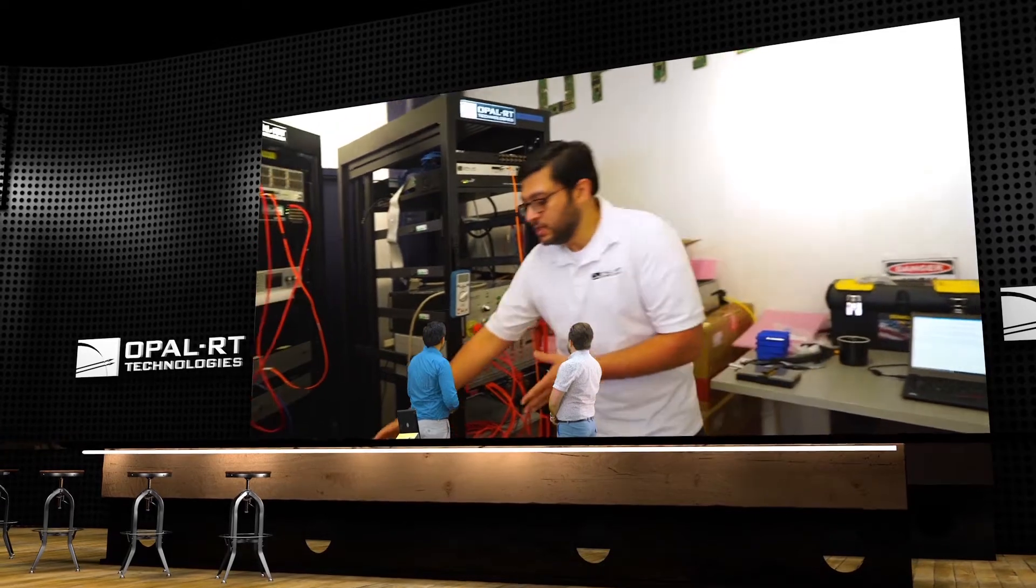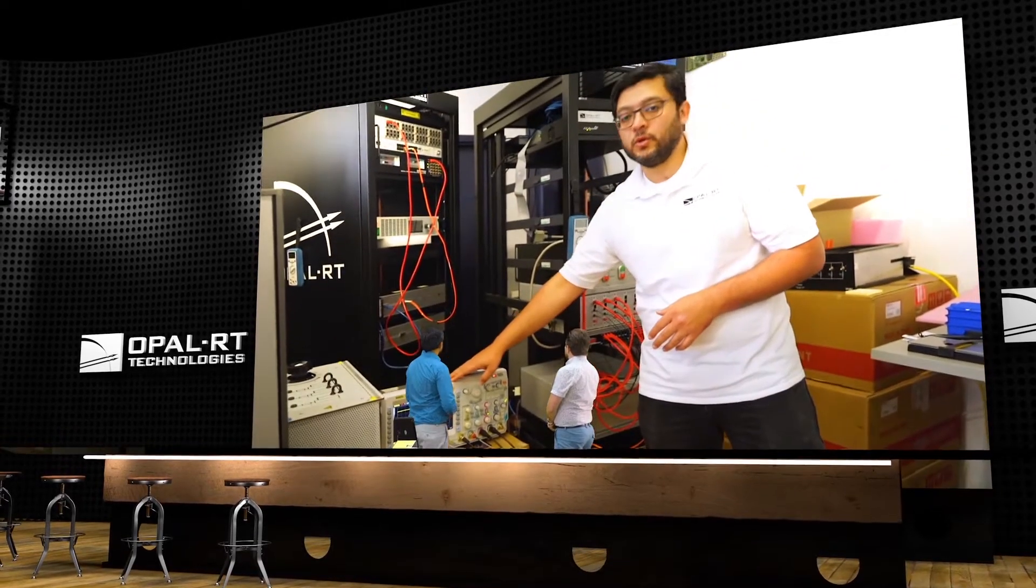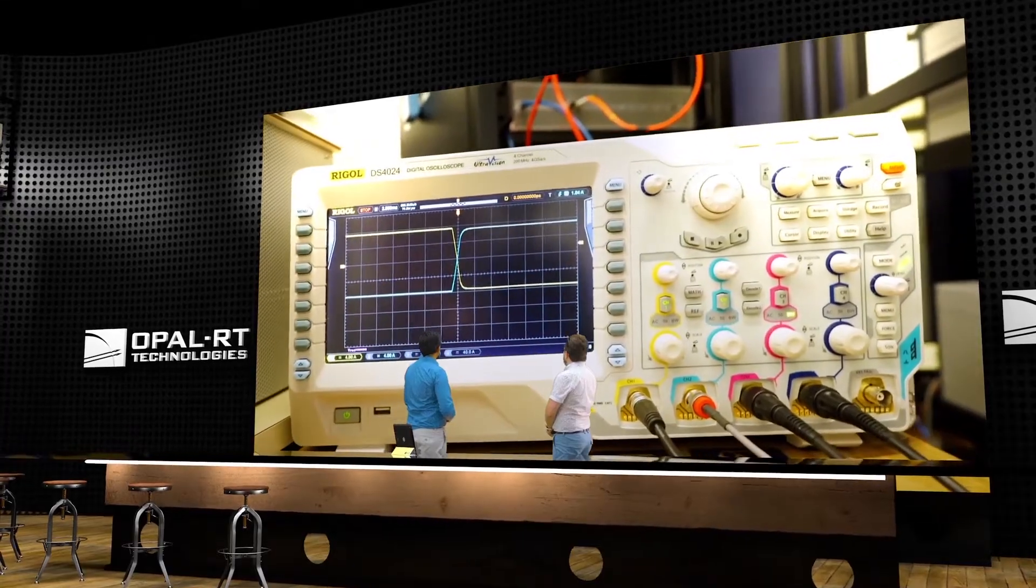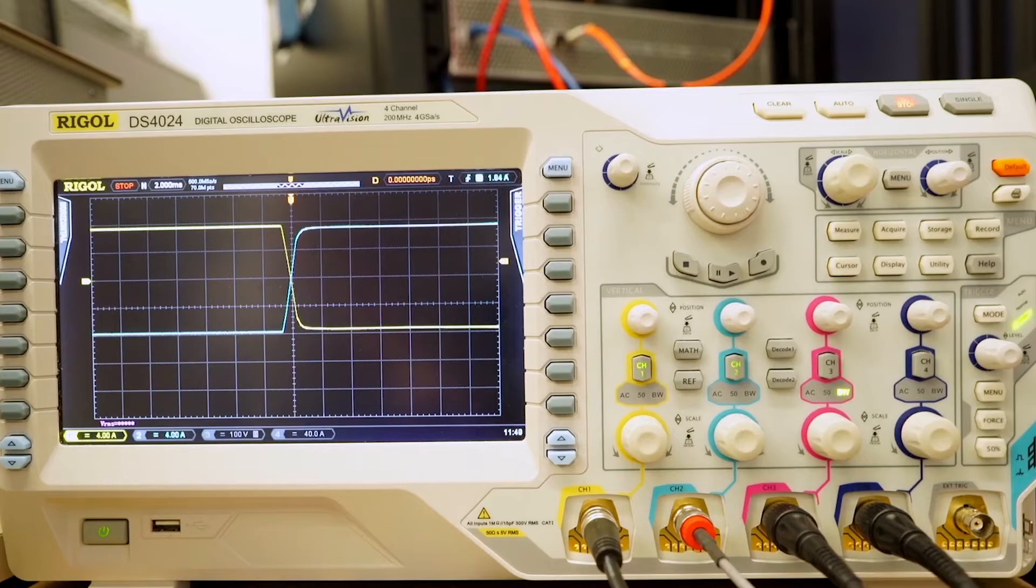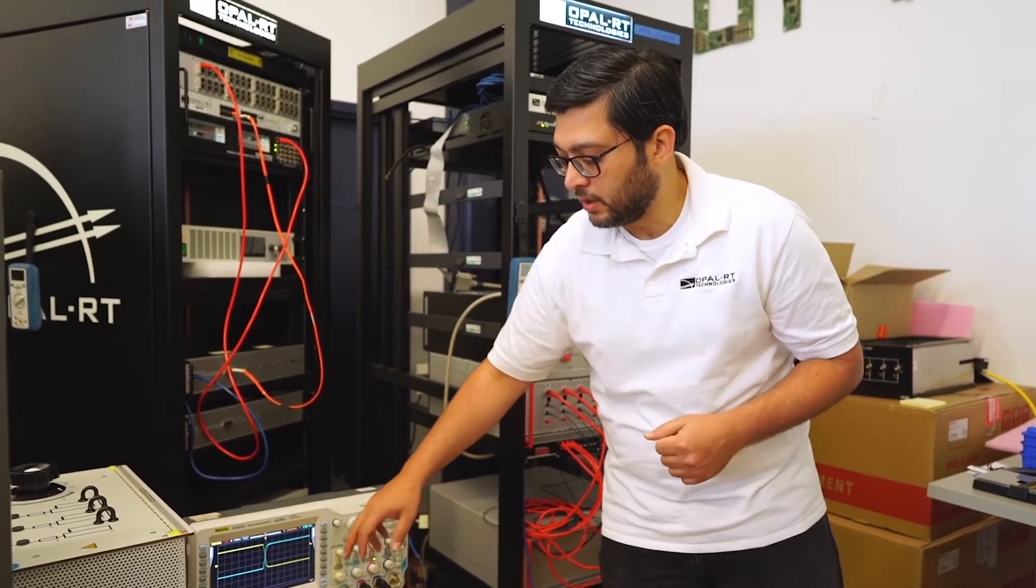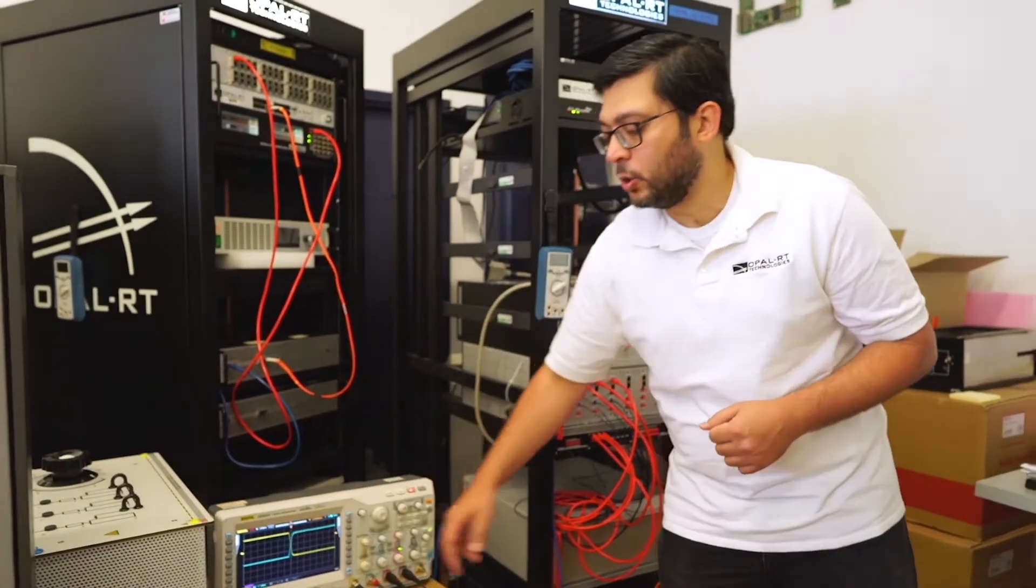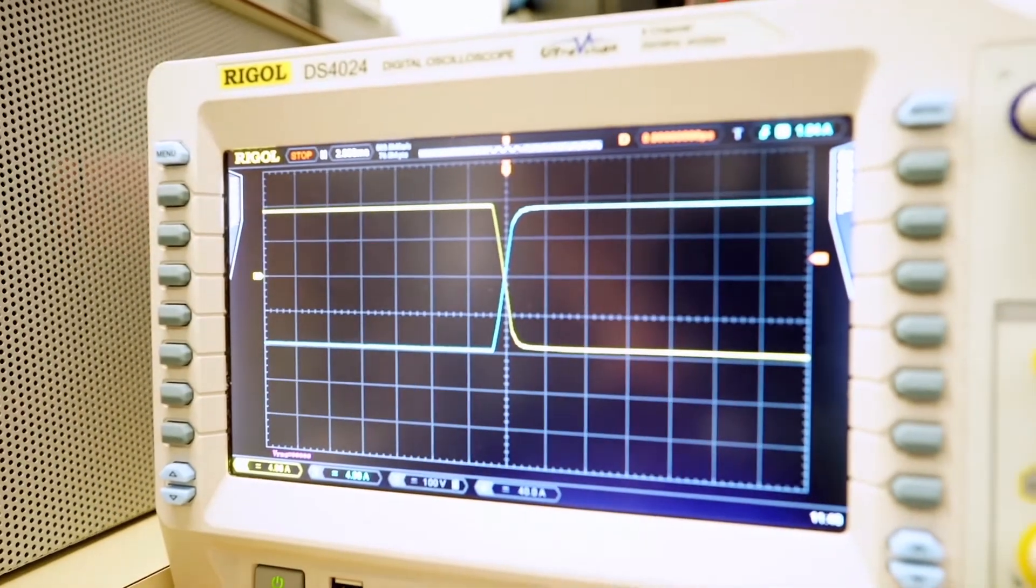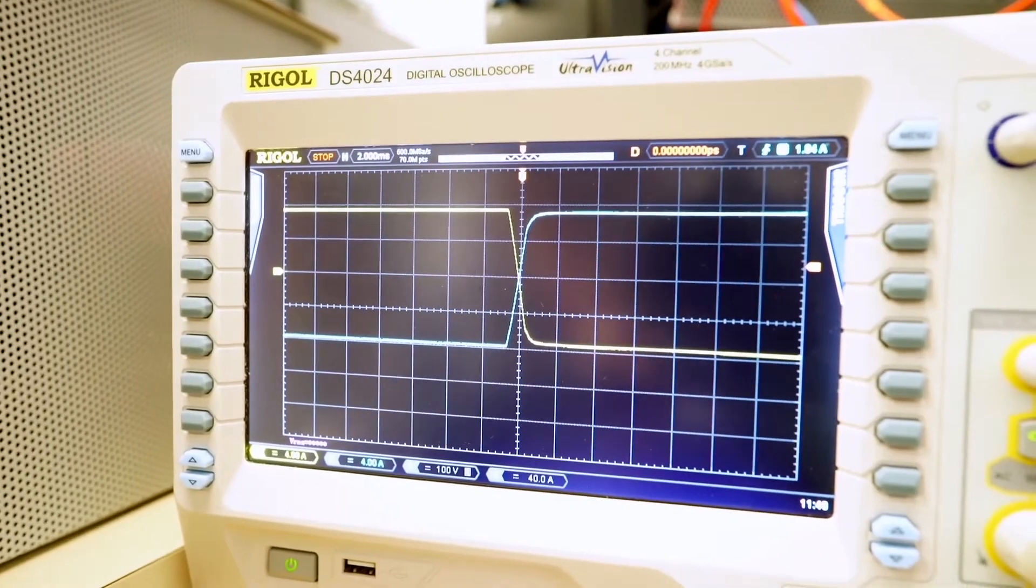The first amplifier group emulates a DC network, producing a 50 volt DC voltage at its output. The second amplifier group acts as a storage DER which is capable of absorbing or sourcing current. On the scope, we see a step change on the current-controlled DER emulator, from sinking current to sourcing current. The blue one shows the group 2 or current-controlled DER current output. The yellow curve shows the network emulator current output. We see a step change from minus 5 to plus 5. Hope you liked the demo.